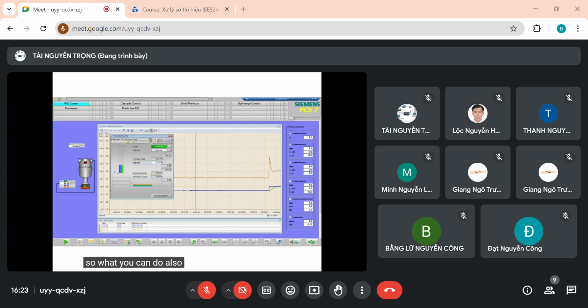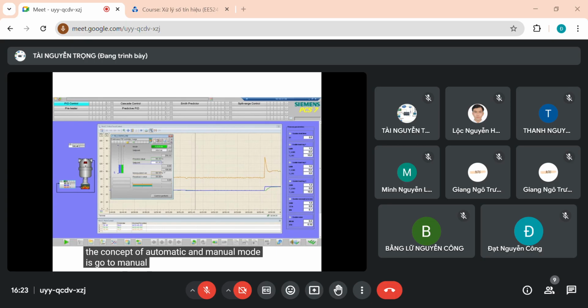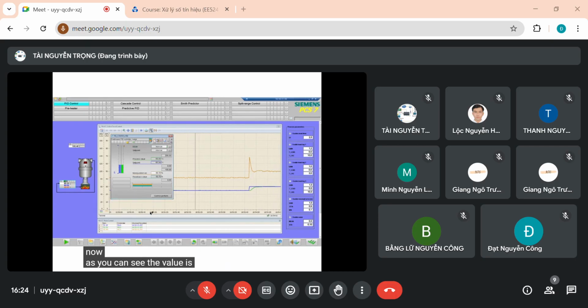So what you can do also to illustrate here the concept of automatic and manual mode is go to manual mode. Observe here that the manipulated value MV is fluctuating. When the controller goes to manual mode, the last active value in automatic mode will be selected and will have a bumpless transfer. This is illustrated now. As you can see, the value is fixed to its last automatic value.